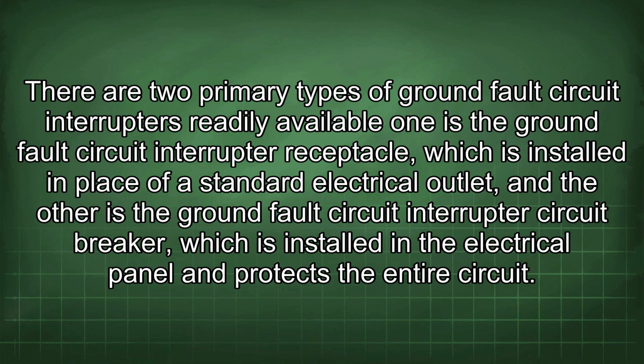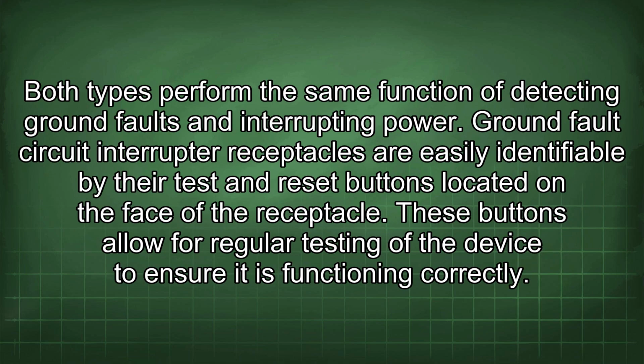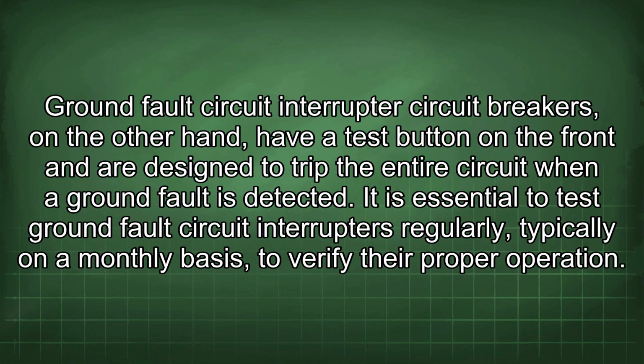One is the ground fault circuit interrupter receptacle, which is installed in place of a standard electrical outlet, and the other is the ground fault circuit interrupter circuit breaker, which is installed in the electrical panel and protects the entire circuit. Both types perform the same function of detecting ground faults and interrupting power. Ground fault circuit interrupter receptacles are easily identifiable by the test and reset buttons located on the face of the receptacle. These buttons allow for regular testing of the device to ensure it is functioning correctly. Ground fault circuit interrupter circuit breakers, on the other hand, have a test button on the front and are designed to trip the entire circuit when a ground fault is detected.